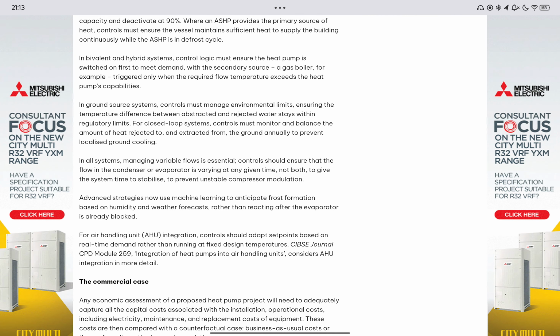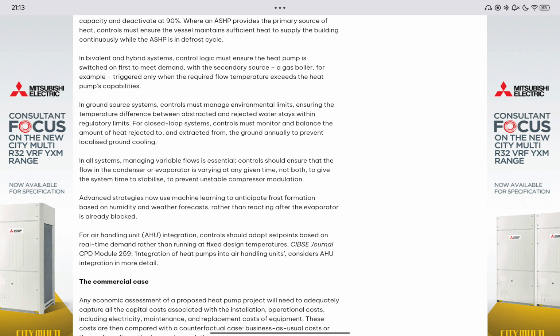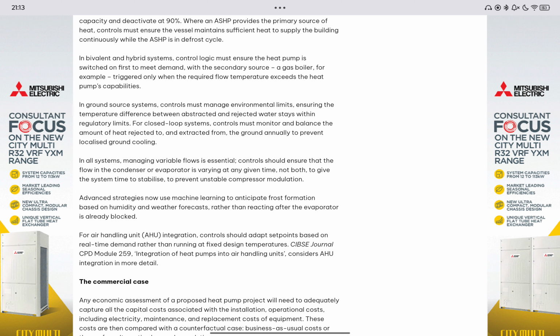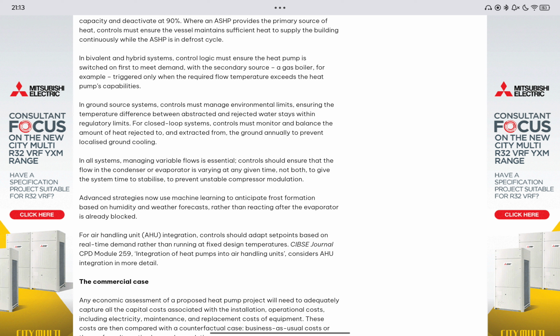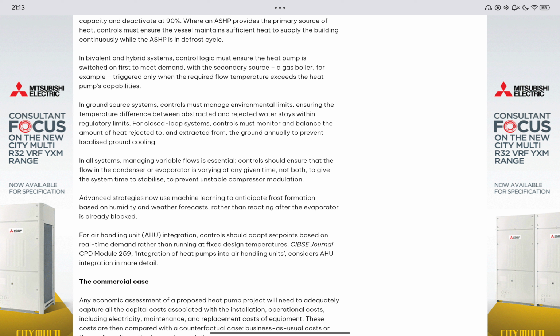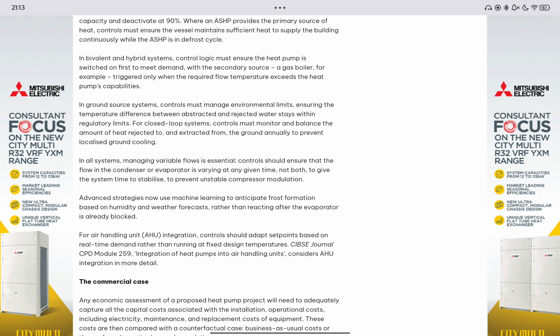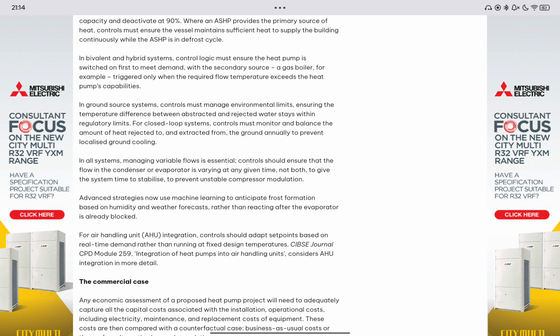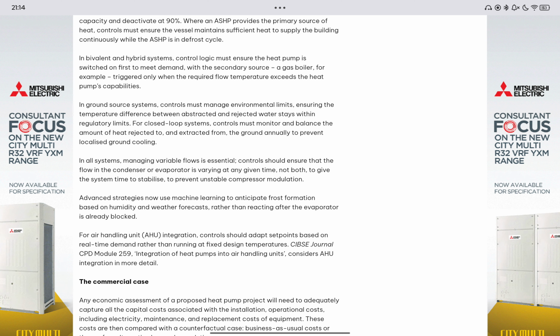in defrost cycle. In bivalent and hybrid systems, the control logic must ensure the heat pump is switched on first to meet demand, with the secondary source, a gas boiler for example, triggered only when the required flow temperature exceeds the heat pump's capabilities. In ground source systems, controls must manage environmental limits, ensuring the temperature difference between abstracted and rejected water stays within regulatory limits. For closed-loop systems, controls must monitor and balance the amount of heat rejected to and extracted from the ground annually to prevent localized ground cooling.